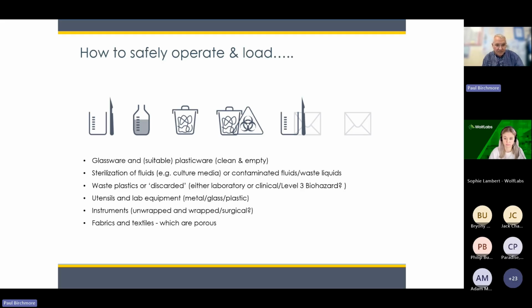But the different types of loads are touched on. Those are typical popular ones listed on the screen there. They can be sterilized, as I've touched on already, at different lengths of time and at different temperatures. But you're going to hear this phrase, I'm going to mention it again, the nominal 121 for 15 minutes, is the sort of default setting, if you like. And what we're also going to find out is that the process of sterilization will have different component parts within the machine, depending on the type of load that we are going to put inside the autoclave. So we'll go through those one by one. And you'll see sometimes that there's mention of additional features that need to be included within the autoclave design to achieve a sterile condition for some of these types of loads. So we need to know what the load is and then have the appropriate features within the autoclave to allow you to complete the process effectively.